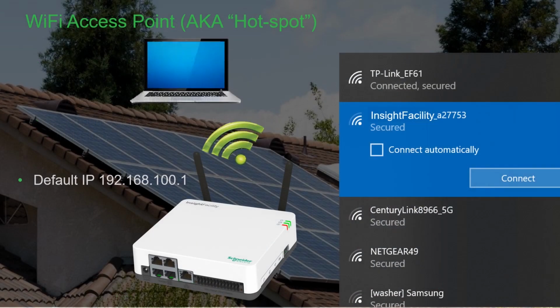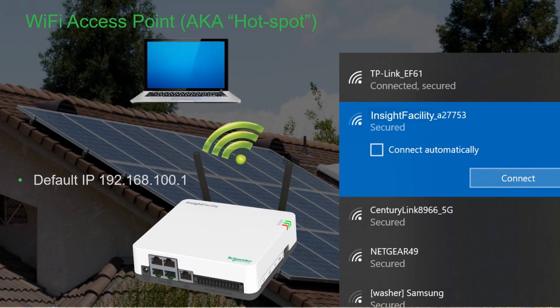If a router is available at the site, you can plug an Ethernet cable from the Ethernet port of InsightHome or InsightFacility to the LAN port of the router, which will in turn communicate with your computer wirelessly if it has that capability, or you can hardwire your computer to the LAN port of the router as well. Then simply plug a thumb drive into the USB port of InsightFacility or InsightHome for about 5 seconds. It'll beep twice, then transfer the thumb drive to your laptop. Look for an HTML file named after the serial number of InsightLocal. Once connected, you can set up InsightLocal for Wi-Fi station mode to remove the hardwired connection if so desired.